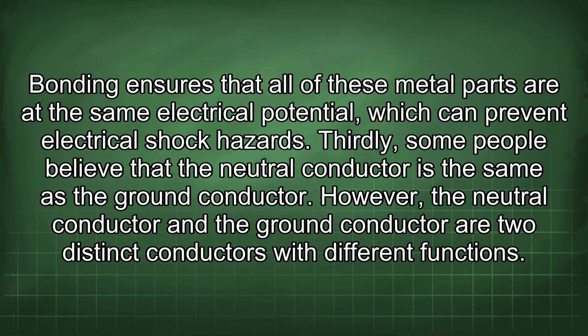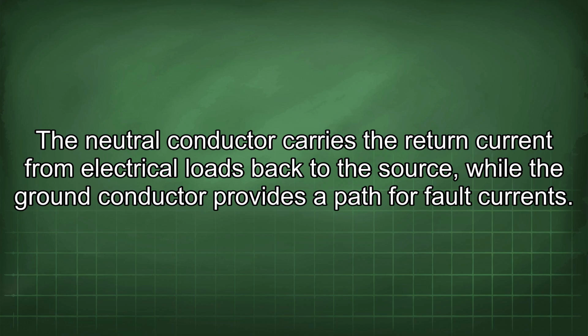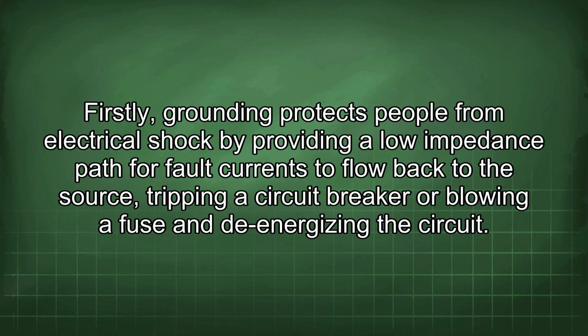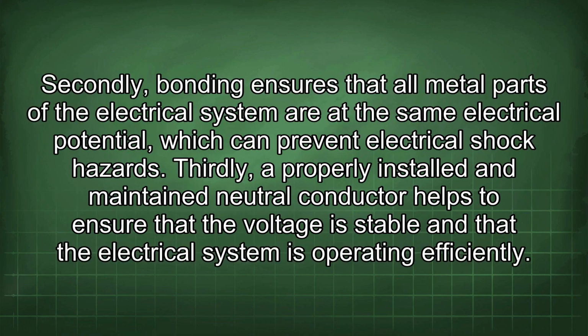Thirdly, some people believe that the neutral conductor is the same as the ground conductor. However, the neutral conductor and the ground conductor are two distinct conductors with different functions. The neutral conductor carries the return current from electrical loads back to the source, while the ground conductor provides a path for fault currents. Firstly, grounding protects people from electrical shock by providing a low impedance path for fault currents to flow back to the source, tripping a circuit breaker or blowing a fuse and de-energizing the circuit. Secondly, bonding ensures that all metal parts of the electrical system are at the same electrical potential, which can prevent electrical shock hazards. Thirdly, a properly installed and maintained neutral conductor helps to ensure that the voltage is stable and that the electrical system is operating efficiently.